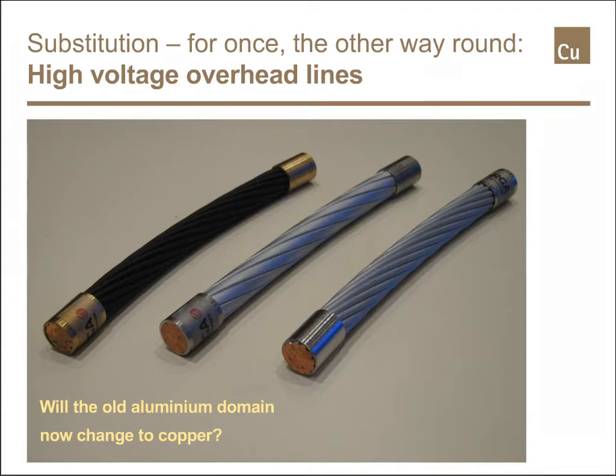But there are situations now in the present days with the energy turnaround and the use of renewable energies that sometimes you need new lines, but you have no space, so it is very difficult to get permissions for new lines, and then the upgrade of an existing line is an option. And in these cases, the copper conductor can help. These conductors are actually made of a so-called copper microalloy. There is much less than 1% of alloyed elements in there, so that the conductivity remains considerably higher than that of aluminium, but the material is very hard, has a high operating temperature and a low sag, and therefore can be operated at temperatures up to 180 degrees Celsius, while aluminium goes only up to 80 degrees Celsius.